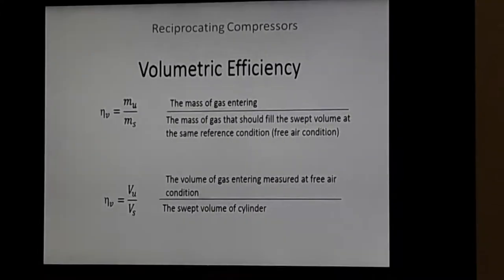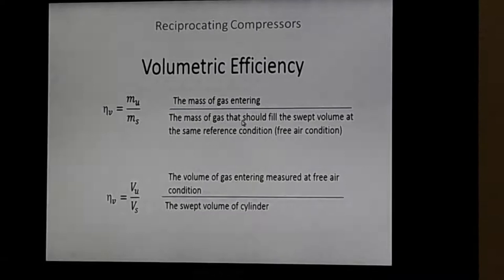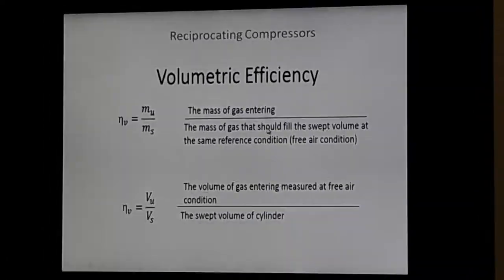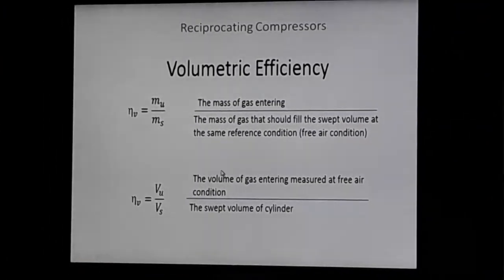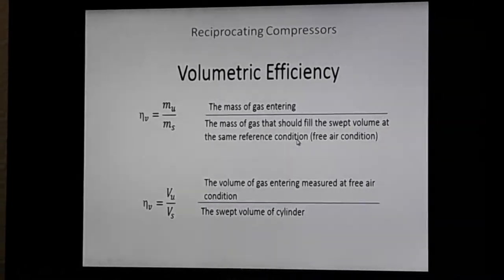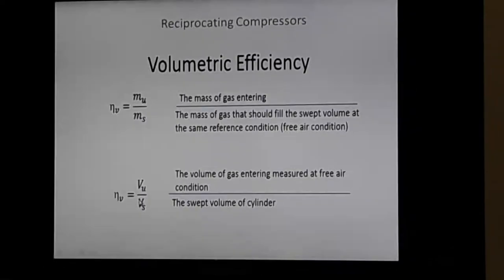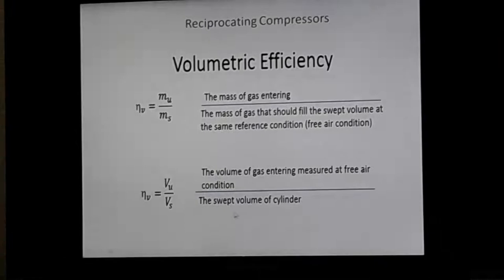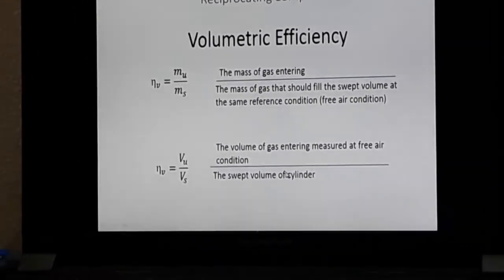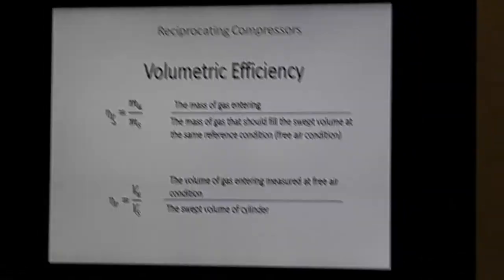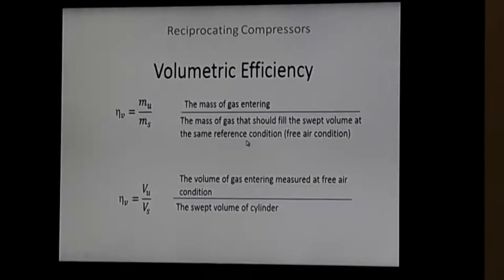Now let us discuss volumetric efficiency. It is the ratio of the mass of gas actually entering the cylinder to the mass of gas that should fill the swept volume at the same reference condition, that is at free air conditions. Alternatively, volumetric efficiency is the volume of gas entering measured at free air conditions divided by the swept volume V_s, written as η_v = V_u / V_s, or in terms of mass as η_v = m_u / m_s.